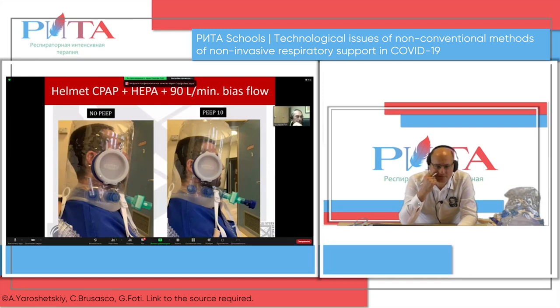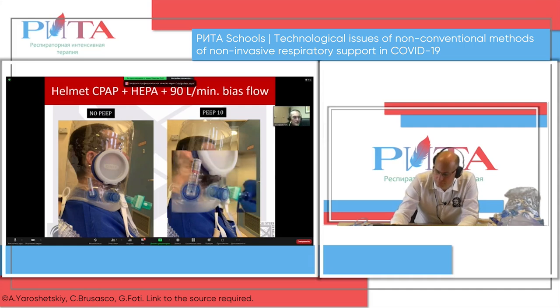This is a helmet CPAP plus an HEPA filter, 90 liters per minute of flow inside the helmet. As you can see here, when you don't set any PEEP, you already have 4-5 centimeters of water. If you set PEEP to 10 instead, you get 15. This is something we have to keep in mind.